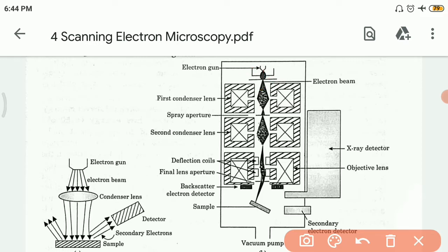Thereafter, the electron beam will pass through a set of condenser lenses, first and second, which are used for focusing this electron beam into a very narrow spot.